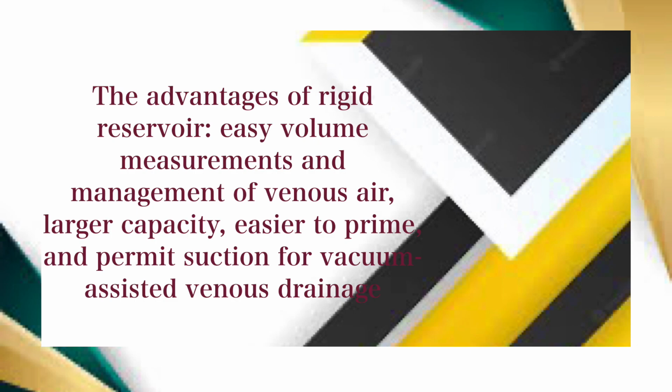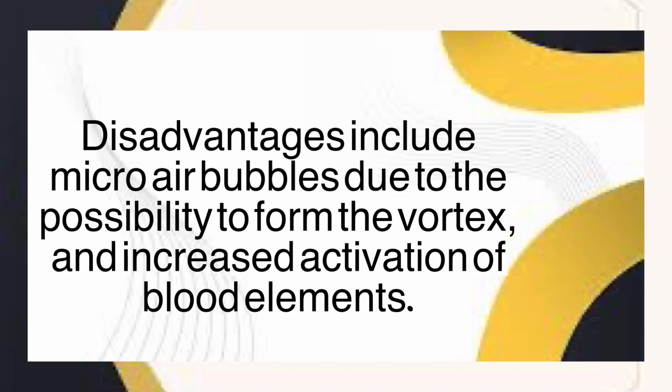The advantages of a rigid reservoir: easy volume measurement and management of venous air, larger capacity, easier to prime, and it permits suction from vacuum to assist venous drainage. Disadvantages include micro air bubbles due to the possibility of forming a vortex, and increased activation of blood elements.